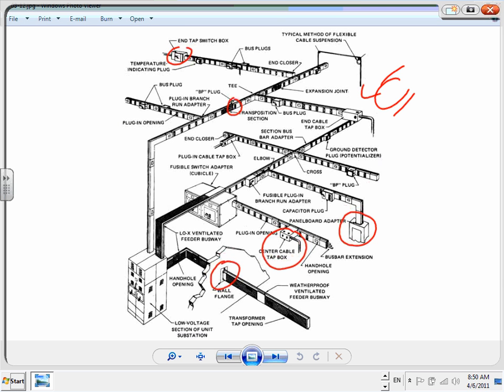Plug-in busway, but you can tap into it with a cable. You can feed a panel. You can go from a switchgear into an MCC, like it shows over here. You can make the whole wiring system a busway wiring system. Feeder-wise, my opinion is that if you're to pull a feeder, it doesn't make sense to pull a feeder busway less than 1000 amps. It just doesn't make sense. A feeder, a plug-in, 225, no problem.